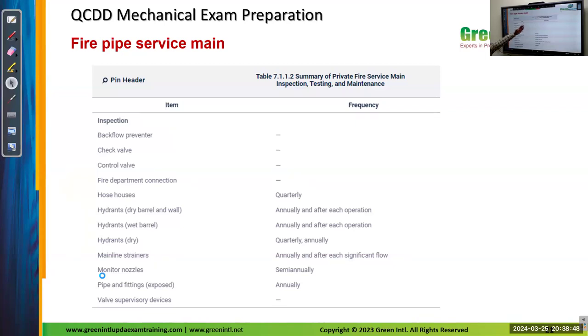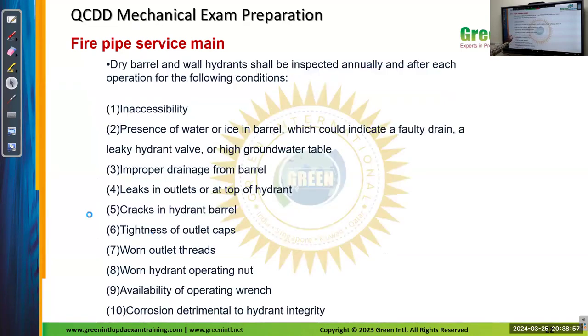And inspection of private service mains. So you will check the valves and hydrants with their frequency, and the testing is also available in parallel. So fire service mains, dry barrel and wall hydrants. We have studied wet barrel systems and dry barrel systems. They shall be inspected annually and after each operation for the following conditions: inaccessibility, presence of water or ice in the barrel, improper drainage from the barrel, leak in the outlet, cracks. This is like a checklist. So we will check all these things.